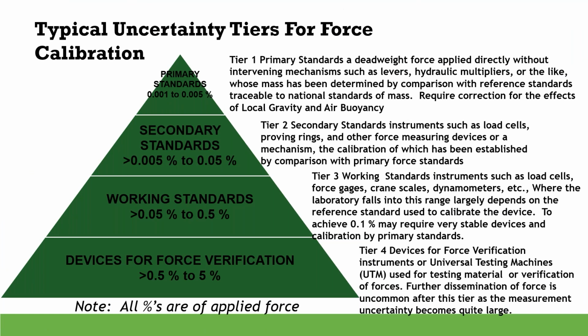So that's some of how to do it, but what we typically get, because people ask, is how good can my system be? E74 lists typical uncertainty tiers for force calibration. You get primary standards, which are dead weights, calibrated to the SI, adjusted for air buoyancy, material density, and local gravity. So force has been determined there, and that's what you're going to correct for.